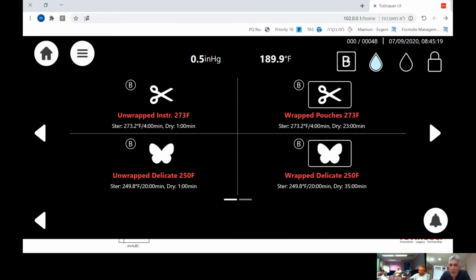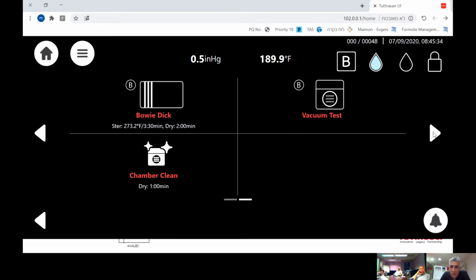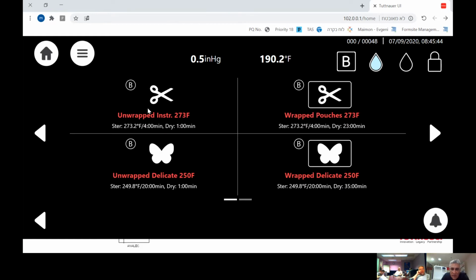Then we have the option to select between class B or class S. We will speak about it later on. Here we get the temperature, the pressure and the programs. You can move to the next page where you can see the Bowie-Dick, chamber clean, and vacuum test, leak test, and back to the other programs. These are the default programs. Once the door is closed and you try to choose a program, you can't. So in that case, you have to open the door.